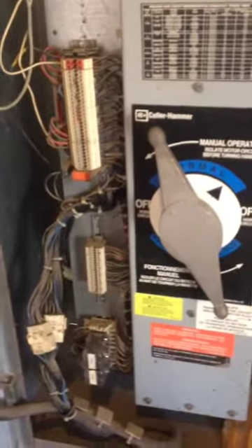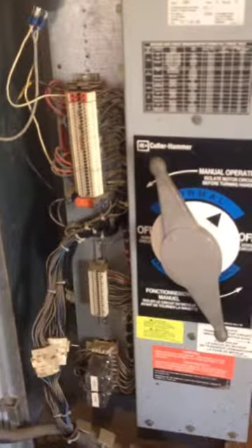So, the next problem we had arise is our inverters. Two times now they have shut down. I'll go over to here. One time when they shut down, the signal on the MATE3 default said AC out short.